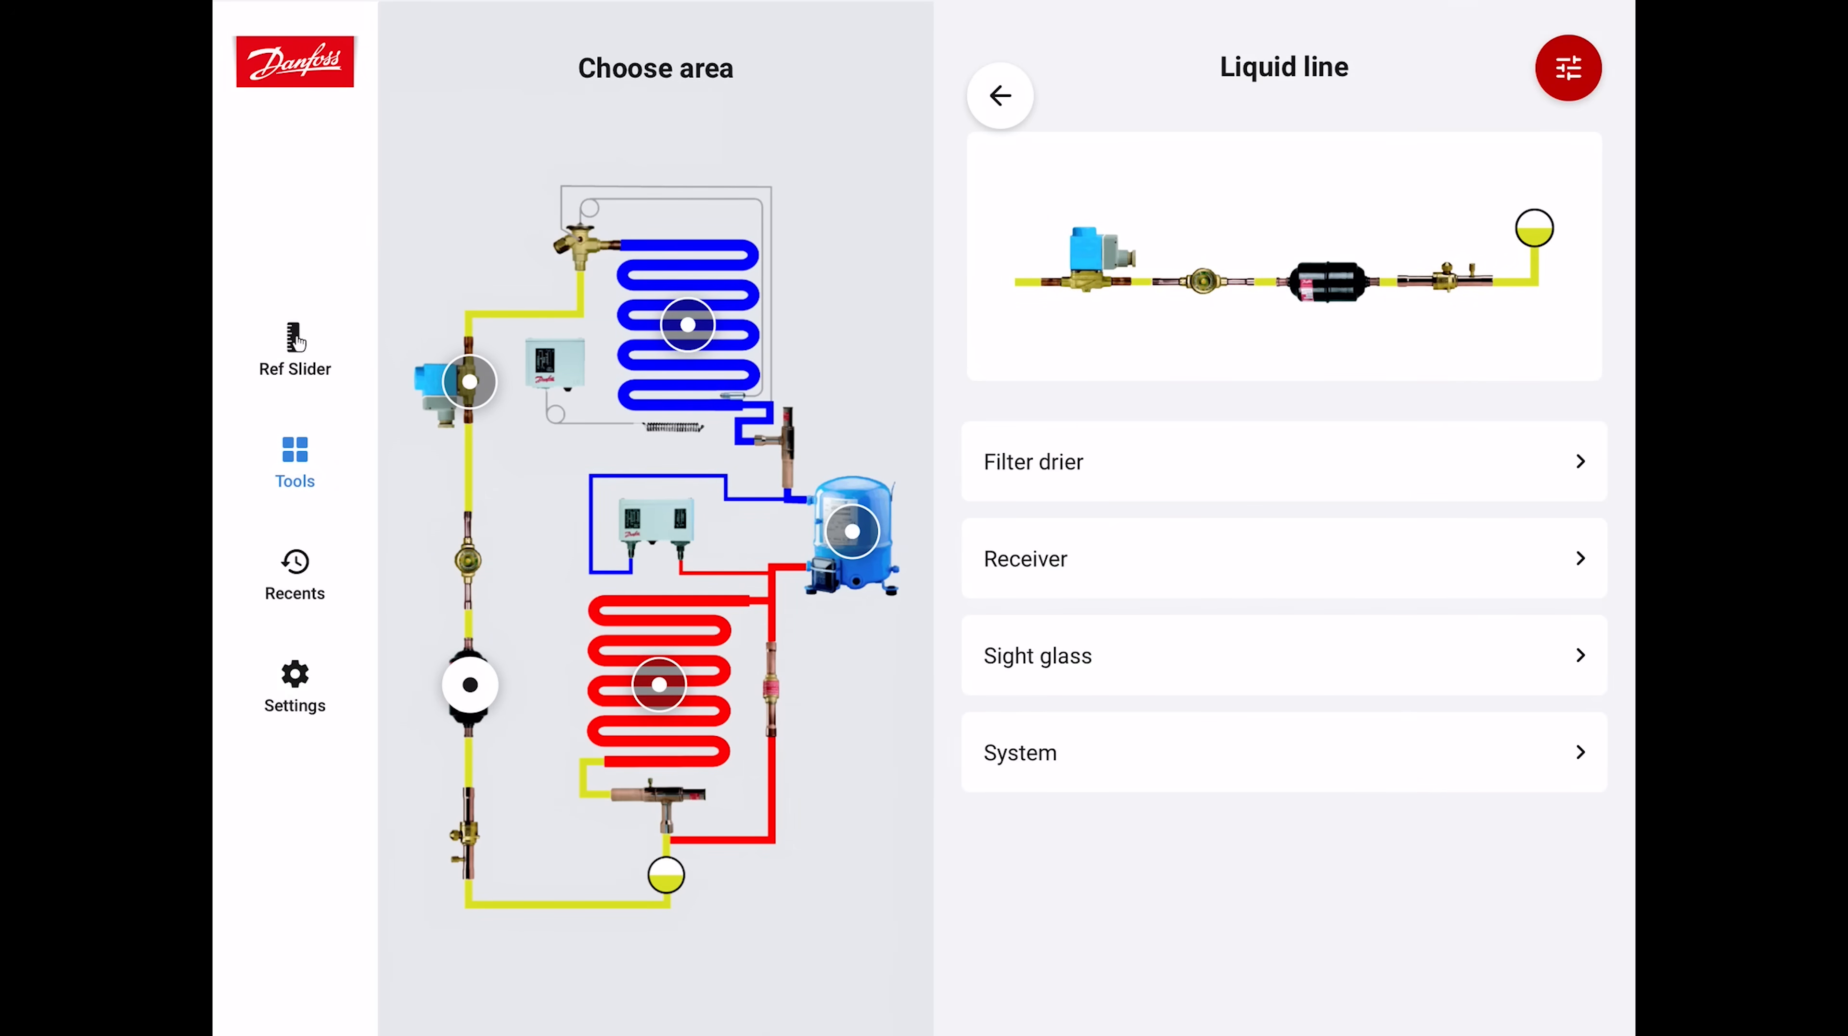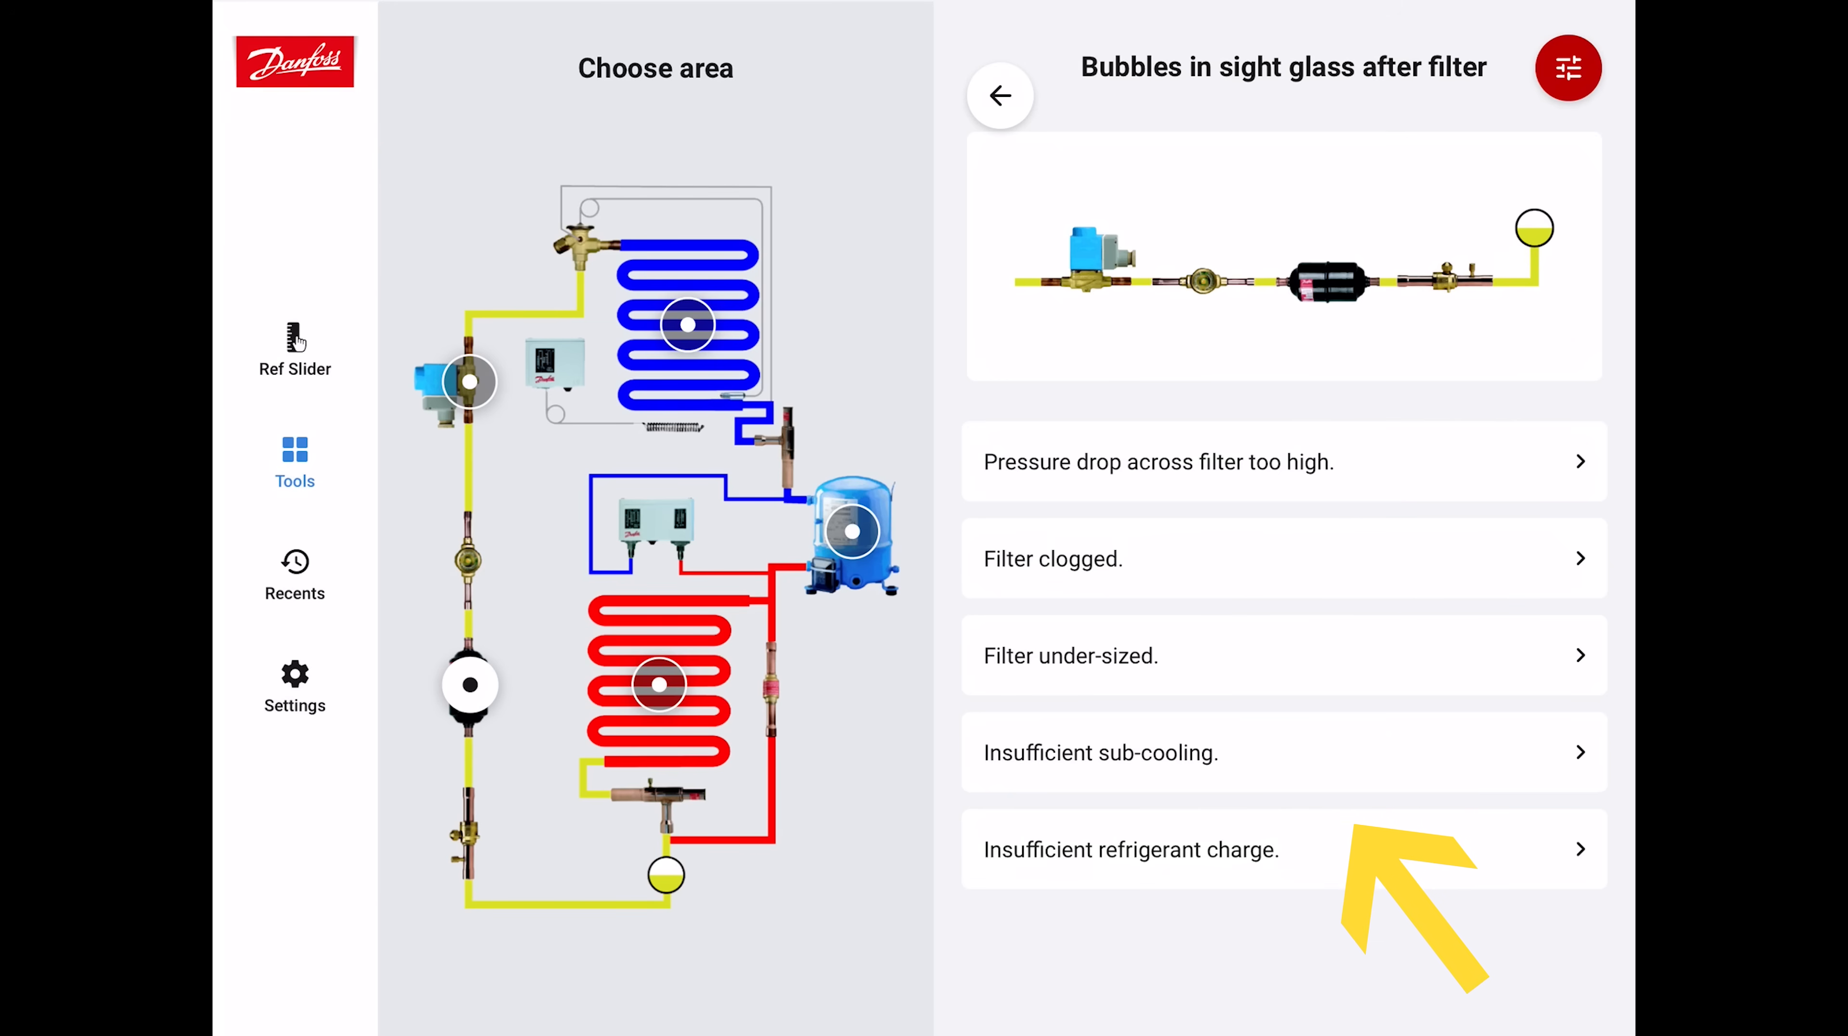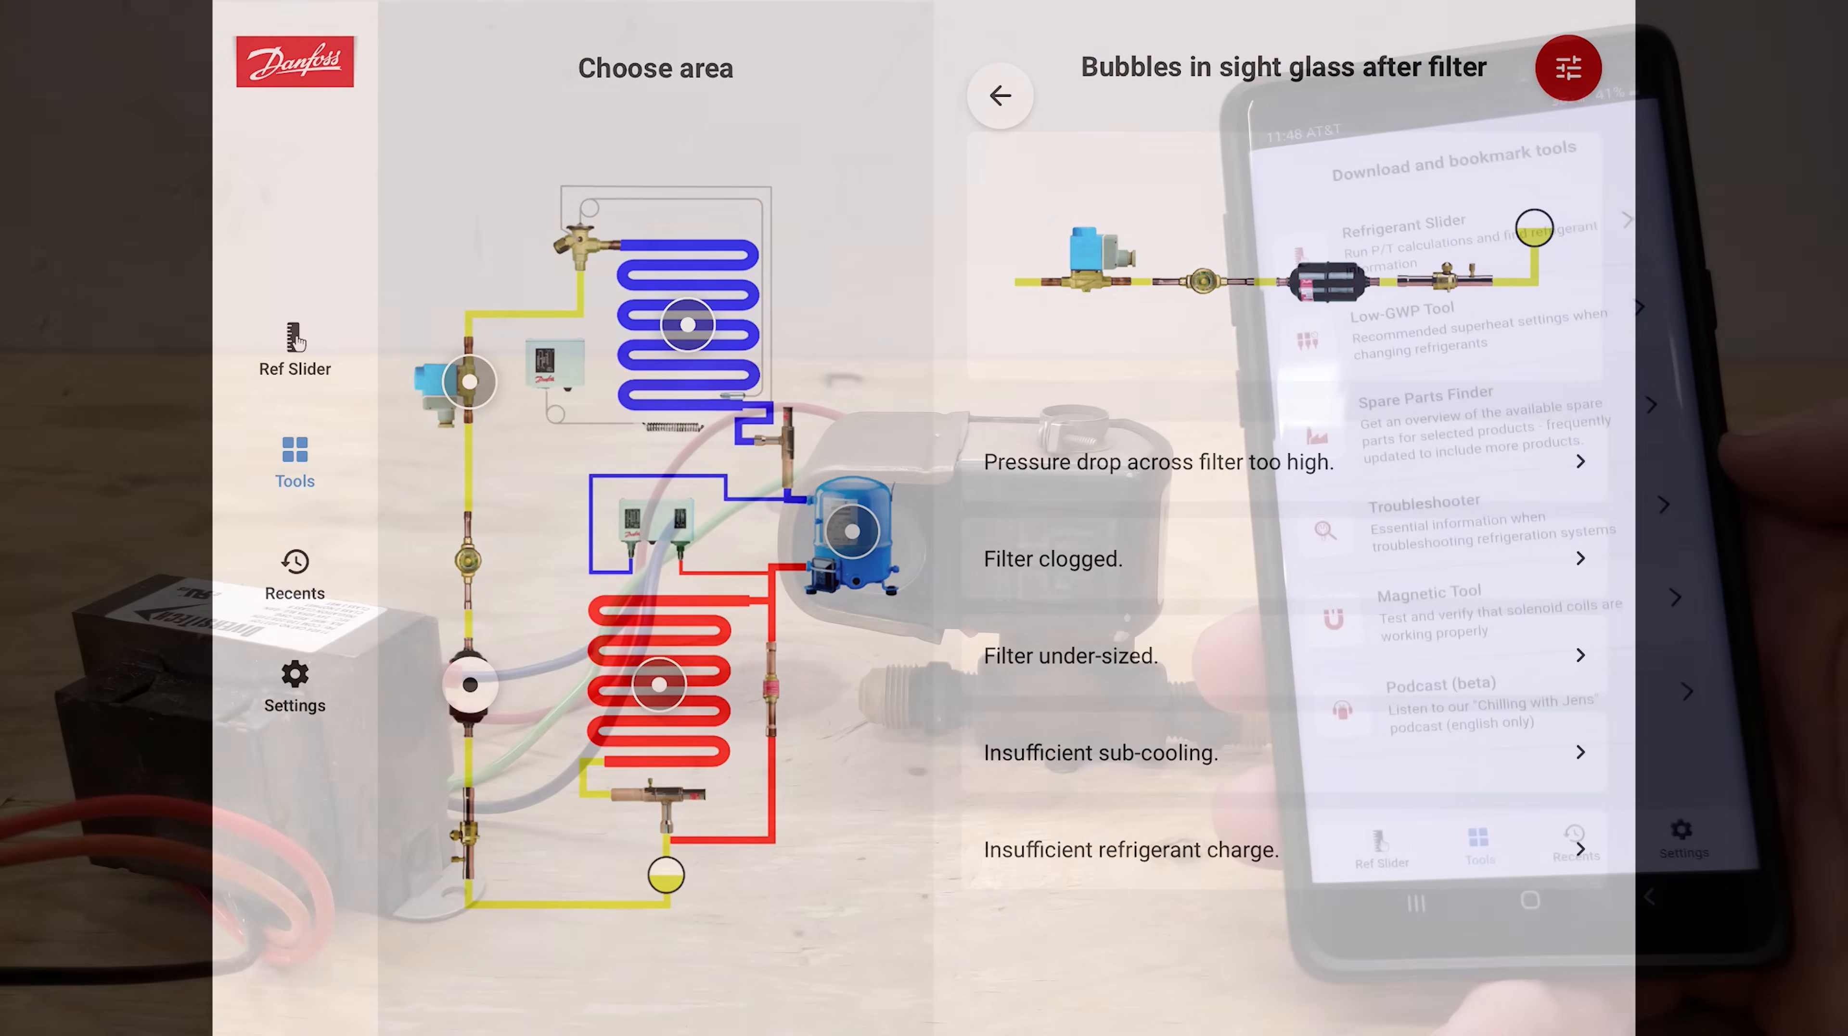Now let's go to the sight glass. If you see bubbles in the sight glass after the filter, let's click on that. It says the pressure drop across the filter is too high, filter dryer's clogged, filter is undersized, insufficient subcooling, insufficient refrigerant charge. It's a bunch of different possible problems that could be the issue there. This is really nice for educating yourself. Whether you want to just practice with this yourself, maybe you have a car ride or something like that, you can pop open the app and do some practice runs to see if you know what the answer could be. Remember that insufficient subcooling could also mean that you have a low refrigerant charge.